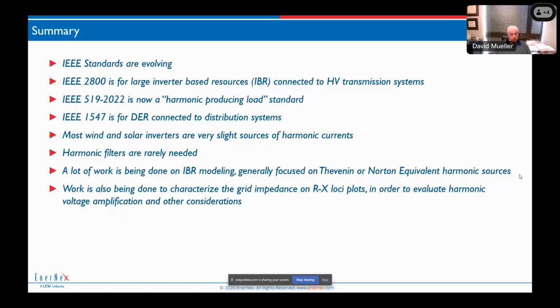There are other countries like Brazil and Australia and European countries where they have to meet harmonic voltage limits, and they do grid studies, and the studies are always conservative and they always show harmonic filters are needed. So they end up putting harmonic filters in all their plants. I don't think we want to get to that. I don't think we want to spend extra money on harmonic filters if we don't need to. And I think it's been proven that probably 90% of the plants do not need harmonic filters, and probably 50% of the plants even have capacitor banks, and still only a very slight fraction of those need harmonic filters.